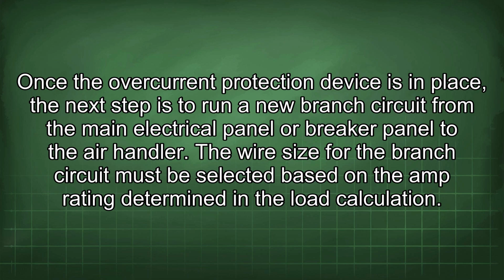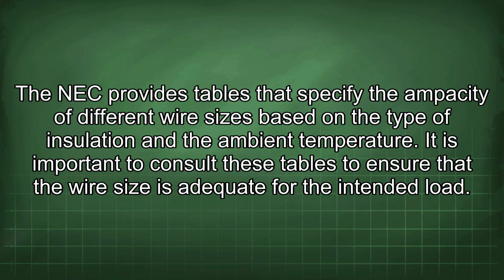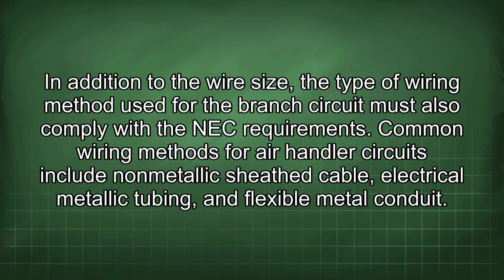Once the overcurrent protection device is in place, the next step is to run a new branch circuit from the main electrical panel or breaker panel to the air handler. The wire size for the branch circuit must be selected based on the amp rating determined in the load calculation. The NEC provides tables that specify the ampacity of different wire sizes based on the type of insulation and the ambient temperature. It is important to consult these tables to ensure that the wire size is adequate for the intended load.